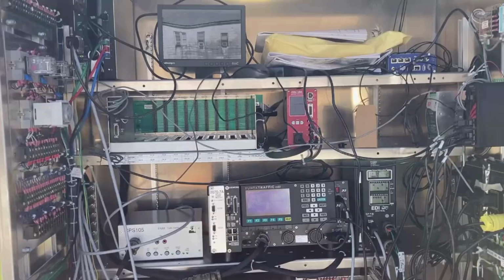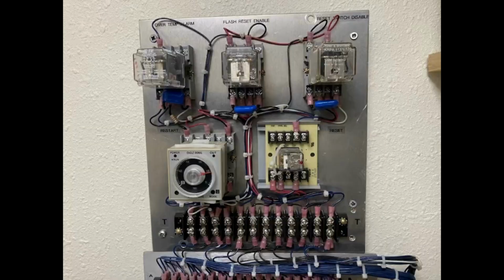But the biggest game changer of all these is my one-shot relay panel that you see here in the traffic signal cabinet. And here it is close up in my in-house setup, just a few relays with some terminal strips, and this is what allows me to remotely reset the conflict monitor if it detects a fault. And having the ability to troubleshoot and repair traffic signals from afar helps me out immensely because I have such a large coverage area to maintain.